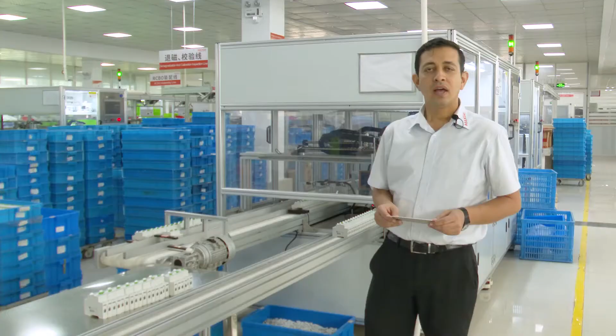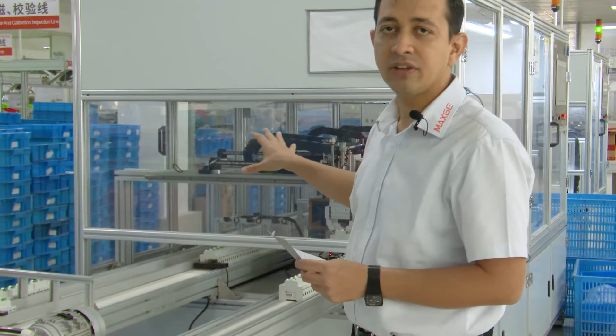Now I have shown you the complete assembly of the RCCB. We have seen 7 processes to finish the RCCB assembly. Now the testing will start, beginning with the demagnetization process. Here in my hand is a process card. The first stage, assembly, is already finished. Now the second stage is demagnetization. This is the machine to check the demagnetization. Let's go and see what this machine checks. This machine has a 4th station to check demagnetization, and during the alternating demagnetization and magnetization mode, the residual tripping current is applied, and we check whether the RCCB trips under that condition.